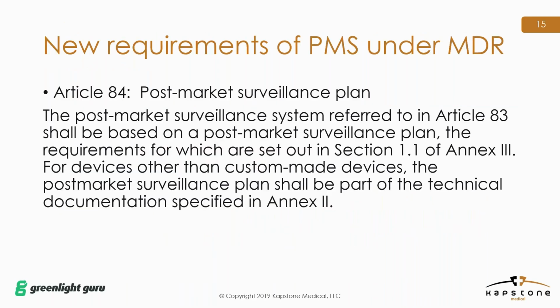One of the next requirements of the new EU MDR is in Article 84, which is the post-market surveillance plan. So this is now one of the newer requirements of the MDR, to have a documented plan for each device or device family. Article 84 specifically states that the post-market surveillance system referred to in Article 83 shall be based on a post-market surveillance plan, and those requirements are set out in Annex 3. And that this plan is part of the technical documentation specified in Annex 2, and Annex 2 talks about technical documentation specific to the device. This is not technical documentation of a PMS system, it's to the device.